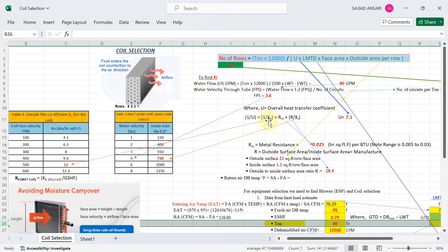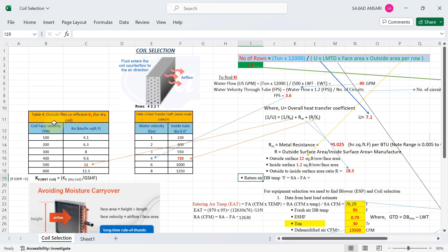k₀ is the outside film coefficient. From Table 4 — 'Outside Film Coefficient k₀ for Dry Coil Based on Coil Face Velocity' — the unit is BTU per hour per square feet per degree Fahrenheit. In our case, face velocity is 500 FPM, so the k₀ value is 11.